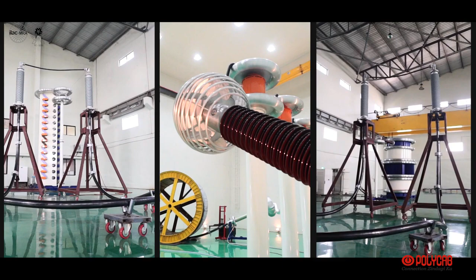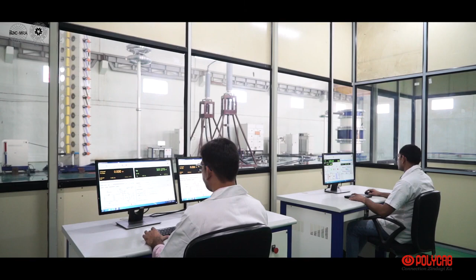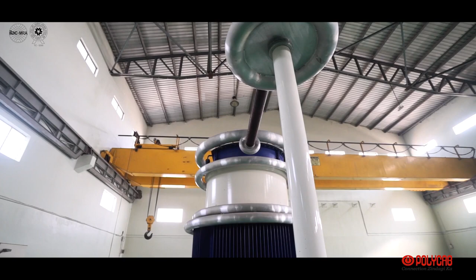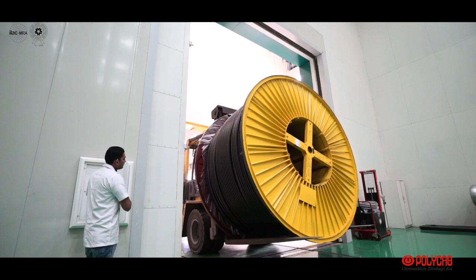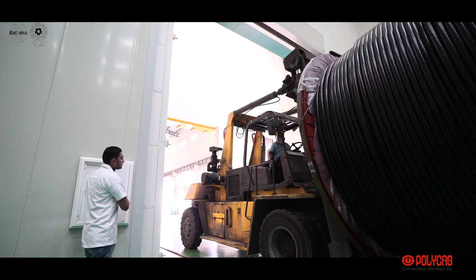Power and energy are the most important aspects of human life. So to transmit more power, Polycab India Limited realized the shift towards the EHV segment, and that brought the inception of the EHV Manufacturing Division. In the year 2012, Polycab India Limited brought stringent norms to upgrade the testing facility to a 132 kV setup. After the progressive and successful journey of 7 years, the company commissioned the most extensive EHV setup available, having a testing facility of 220 kV in the year 2019. Polycab India Limited is now capable of testing a maximum drum length of approximately 4 kilometers, and the turnaround time in the equipment is hardly 2 hours from the commencement of termination work.